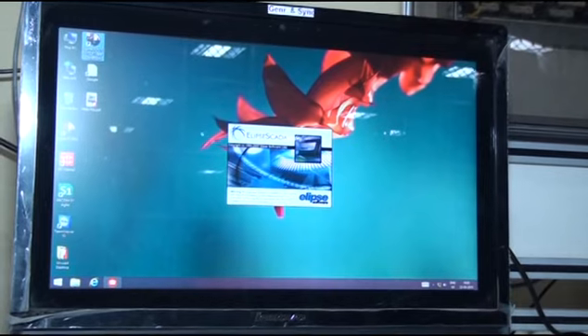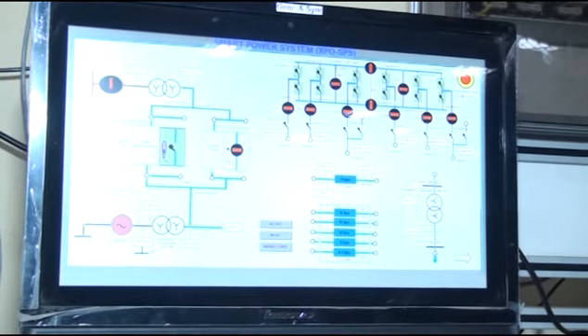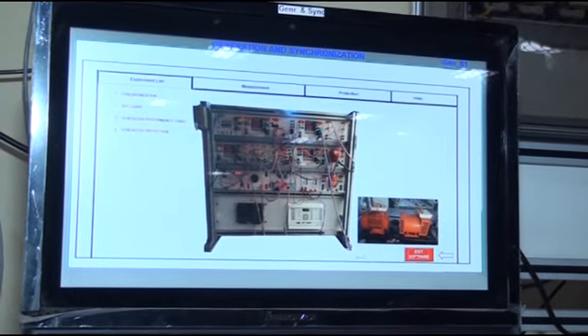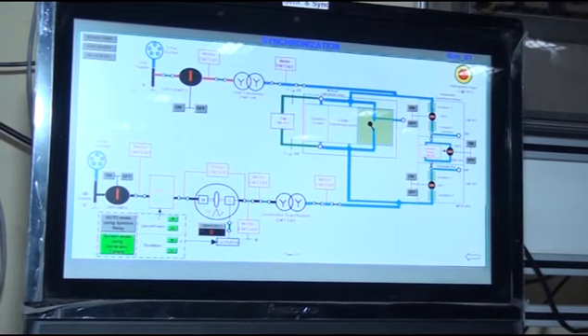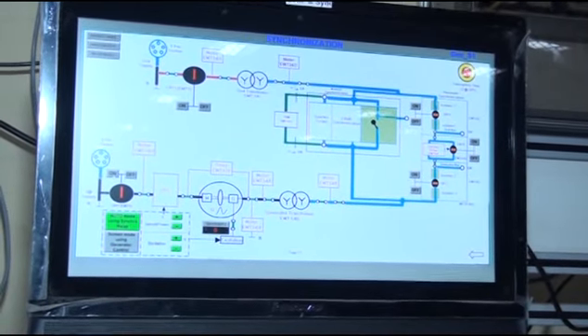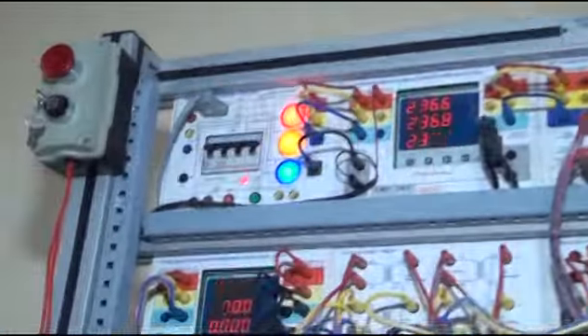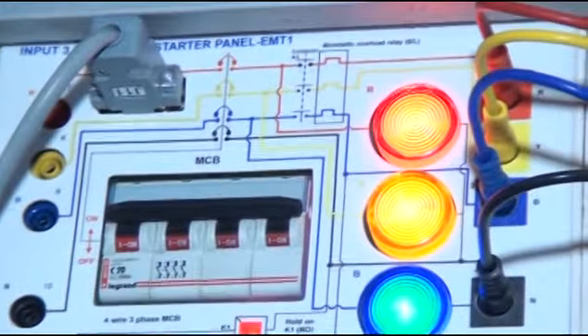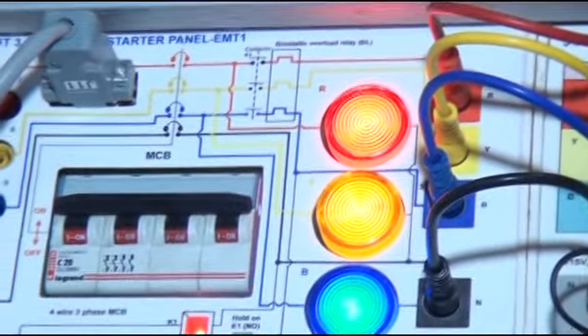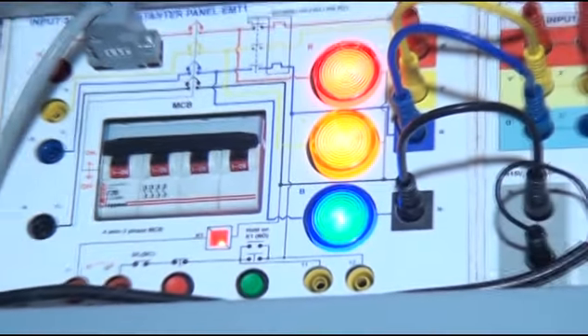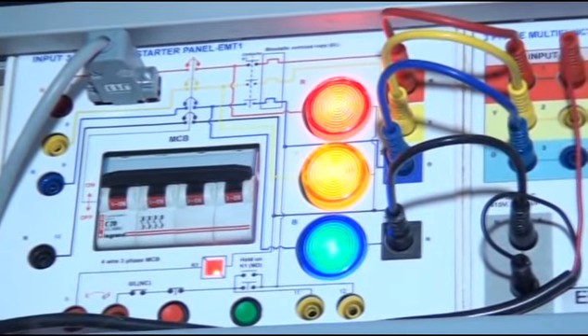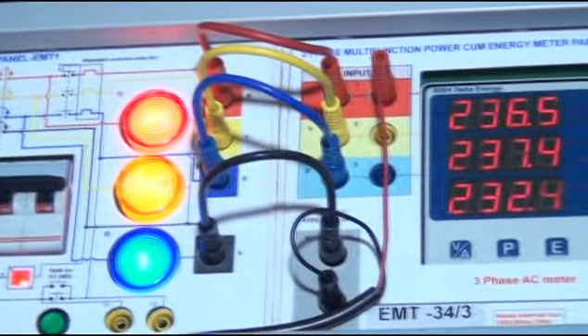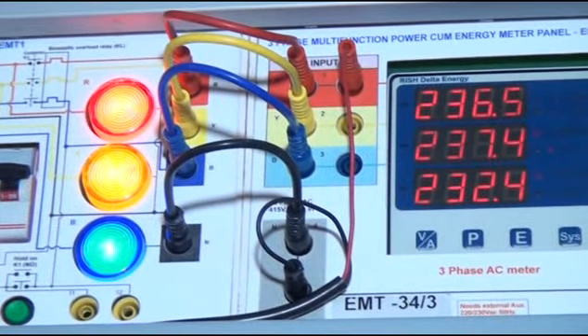This is the generation synchronization touch panel. Open the SCADA screen in the HMI. Here you can see the synchronization screen. Now we are making the input supply EMT1 on using the touch panel by CB11. We observe EMT1 becomes on, and the RYB indicators are glowing. Respective voltages show in the Modbus based multifunction energy meters: 236 volt AC for R phase, 237 volt AC for Y phase, 232 volt for B phase.